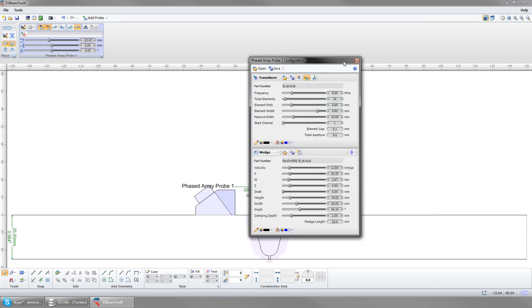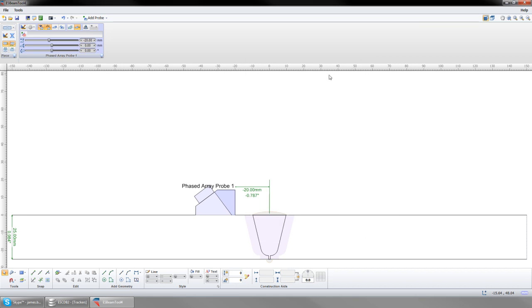Now that we have a probe, we can add a beam set. Select the icon and choose a type of beam set. When a beam set is selected, its configuration window will open, and focal laws can be defined.